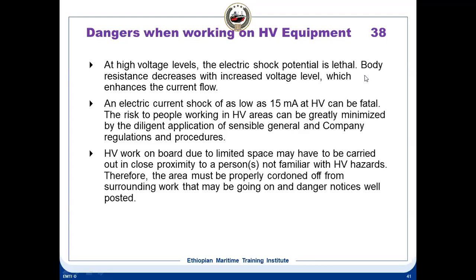And HV work on board, due to the limited space, may be carried out in close proximity to persons not familiar with the HV hazards. So the area must be cordoned off from surrounding work which may be going on, or danger notices well posted. Wherever you work on a switchboard, or suppose you are working on a high voltage motor, the area has to be cordoned off. You have to put up the notice, and also put up blocking so that nobody can come inside. The area has to be isolated. So these are the dangers.